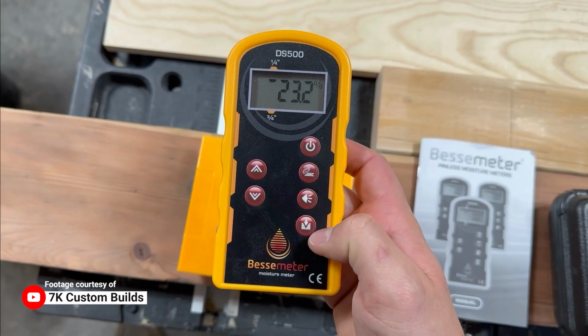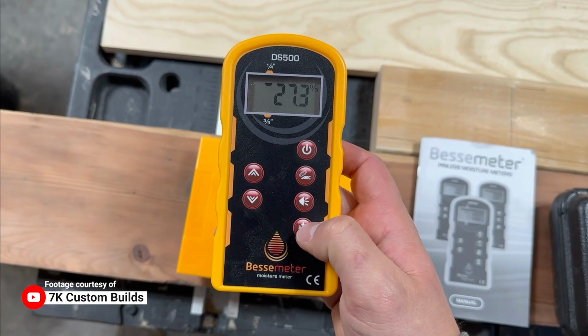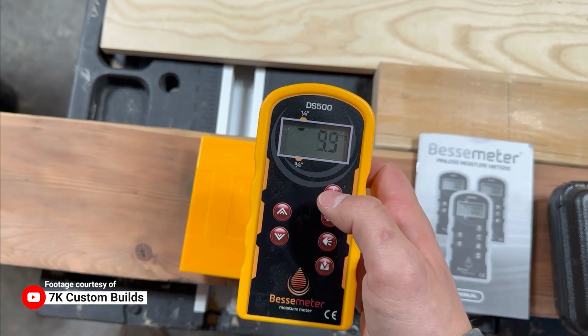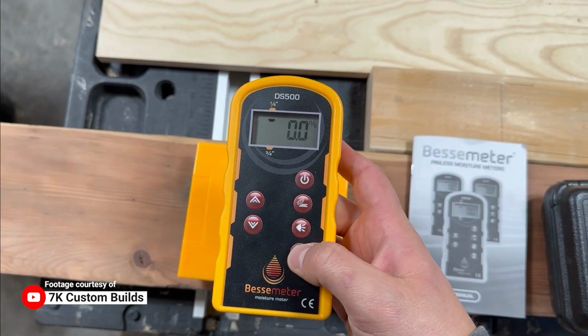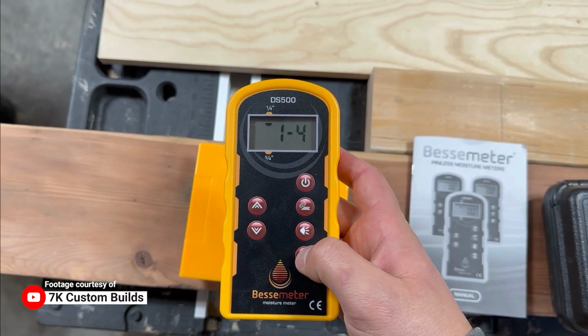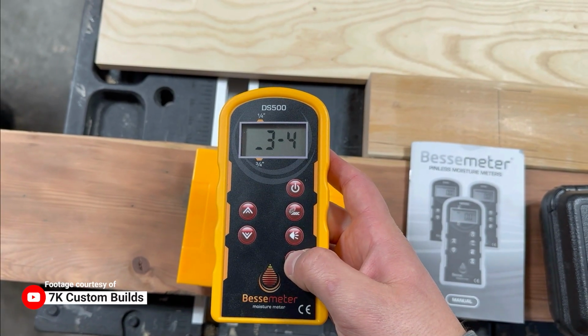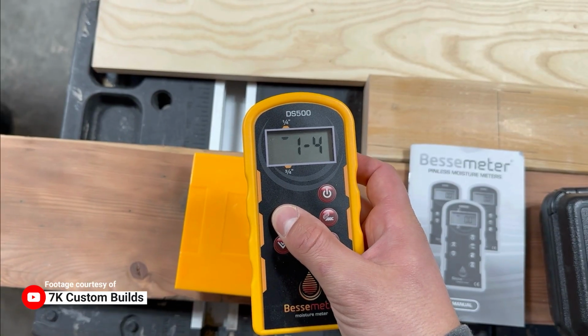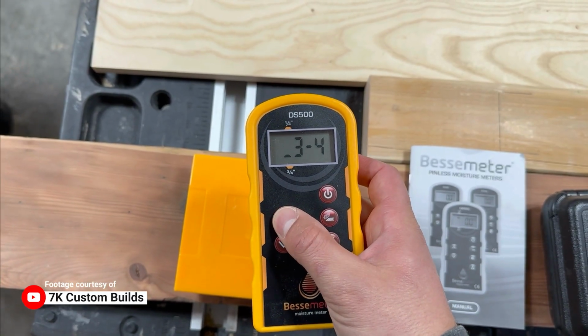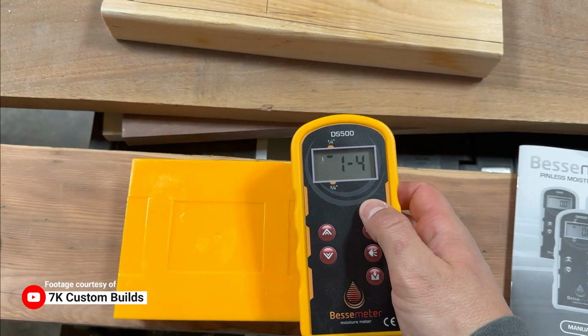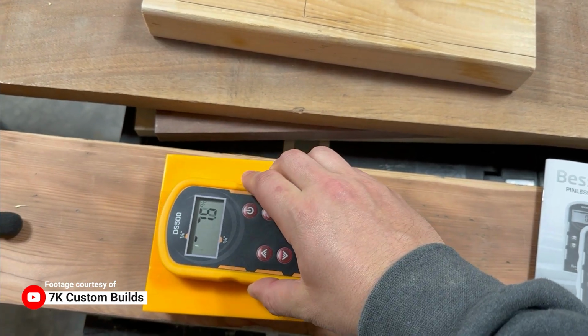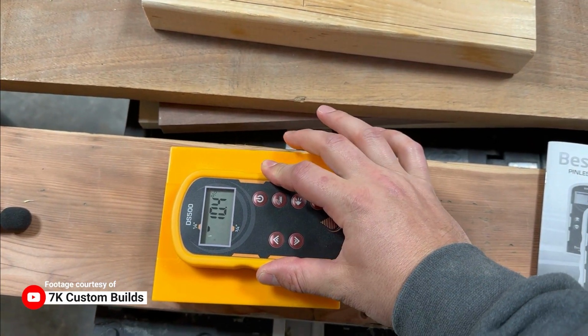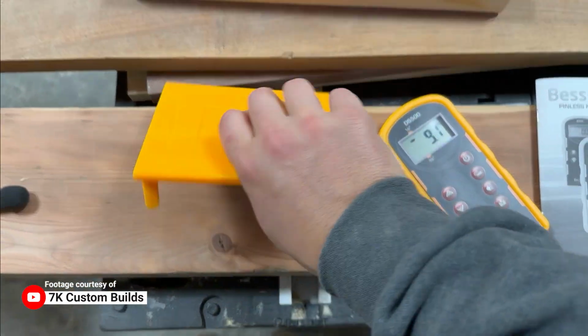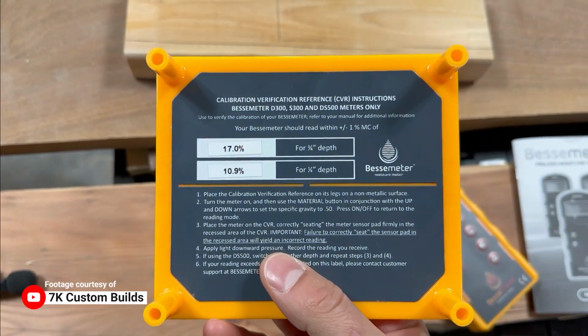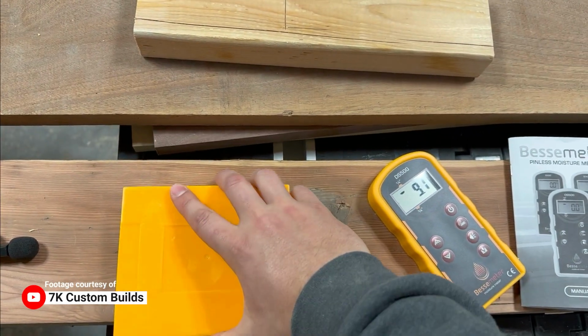This button down here shows you how to change your depth of measurement. So we'll press that button, and then to change it, you either simply press that button again, or you can toggle back and forth with the arrows. Either way. 1/4 inch, save it. And we're reading 10.4%, and that is within our parameters. So we're good on both settings.